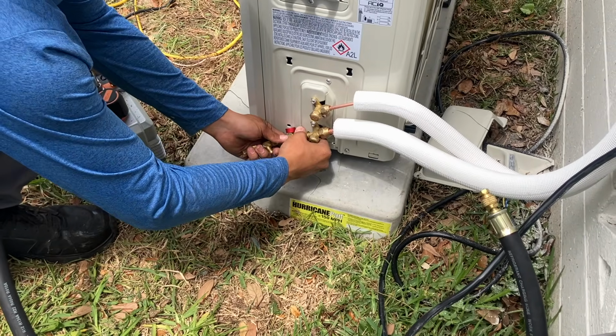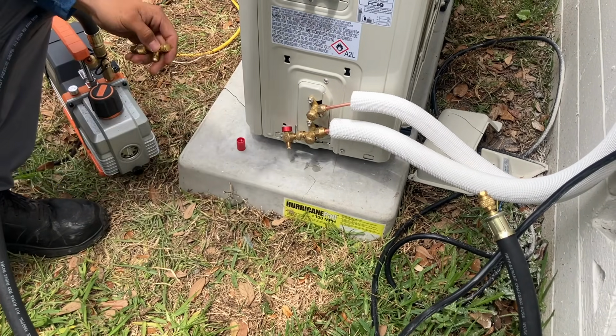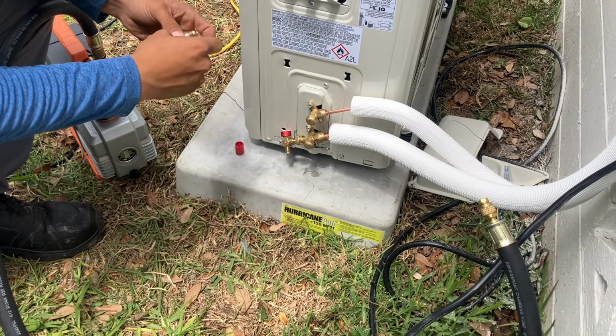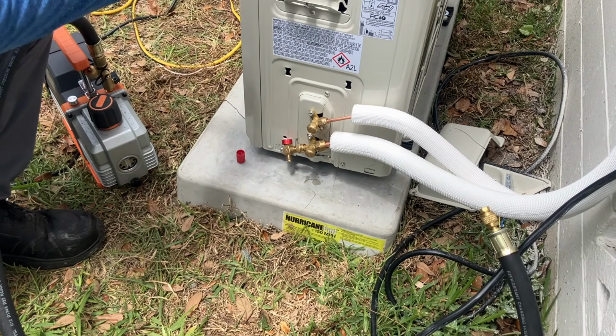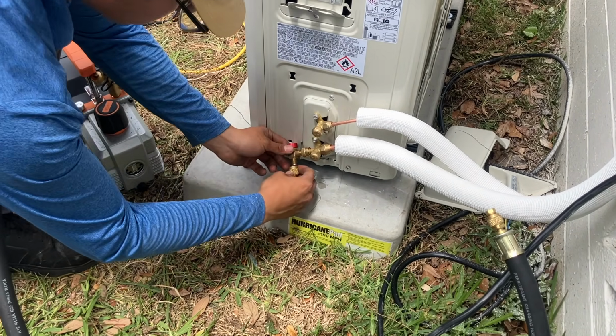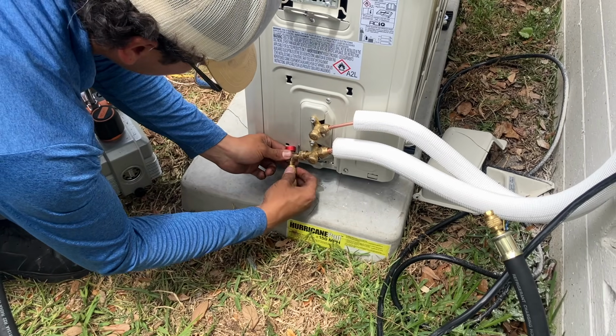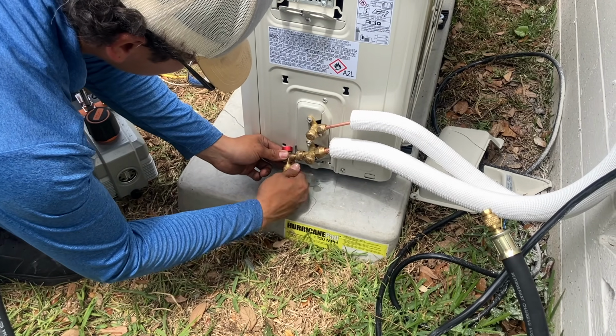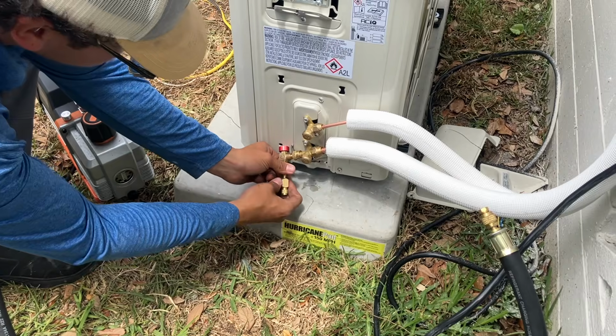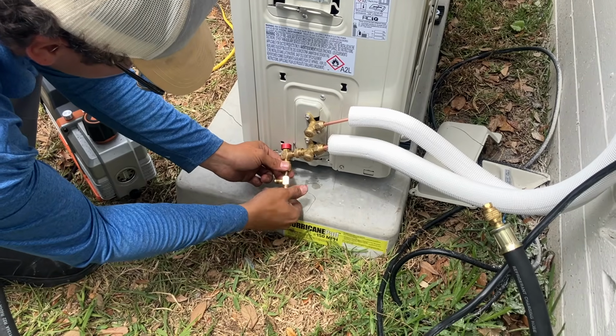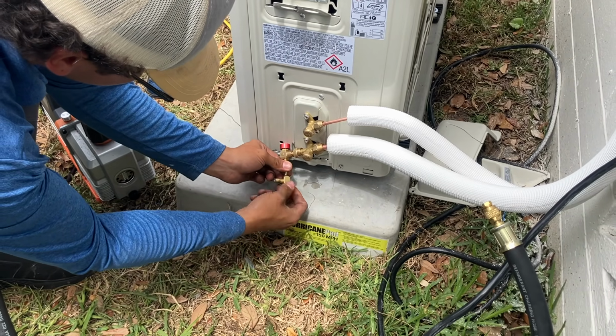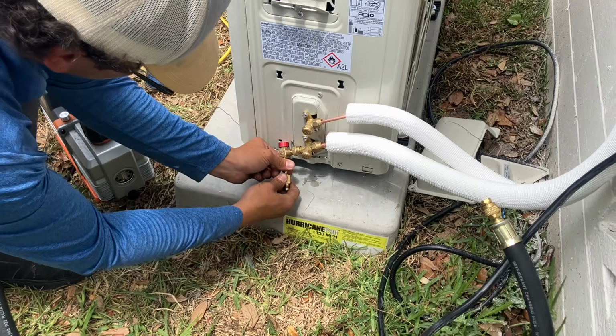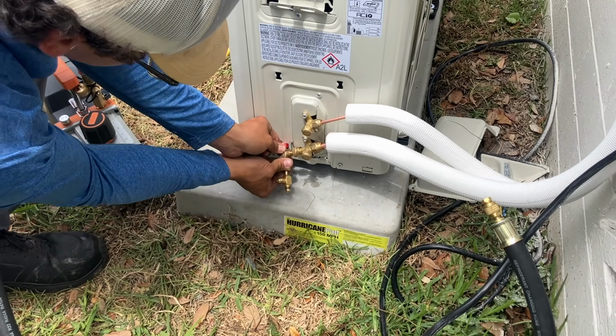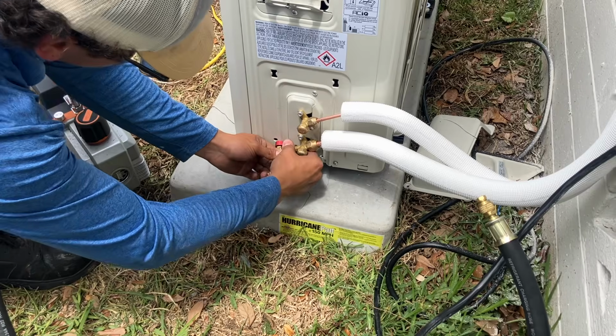Right now Juan is putting a service tool onto that service port. He did not pull the Schrader core, but it's not really a long line—I think we have like 12 feet, 10 feet if that. So this will pump down quickly, even with that Schrader core in place.